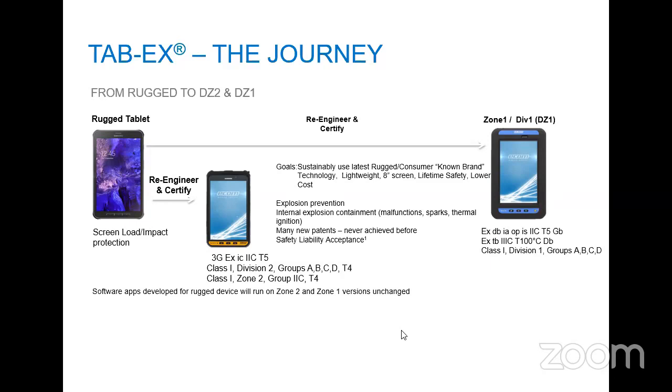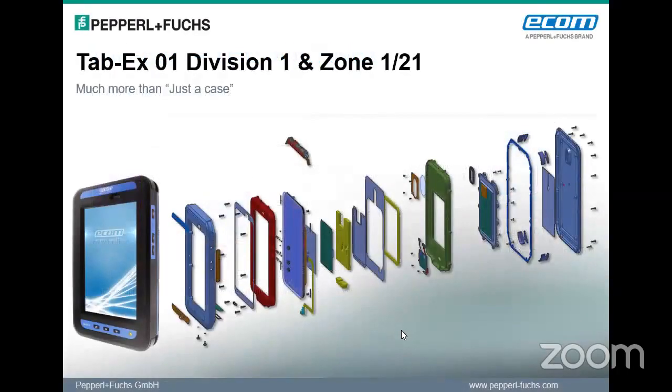See, Justin, the question I would give is, it's not a case around that device. It is a device, because if you take the case off of the device, you're done. This one, you're good. Can you charge the device in the hazardous area? No. It's got to be charged outside the hazardous area. Way back in the day, there were some products that you could charge in the hazardous area, but the extra engineering and cost to make that work and get it certified just didn't make it worth it. So we always shoot for a long battery life. We want to make sure you can get through a 10, 12-hour shift with normal usage, but you can't charge really any of the e-com stuff inside the hazardous area.